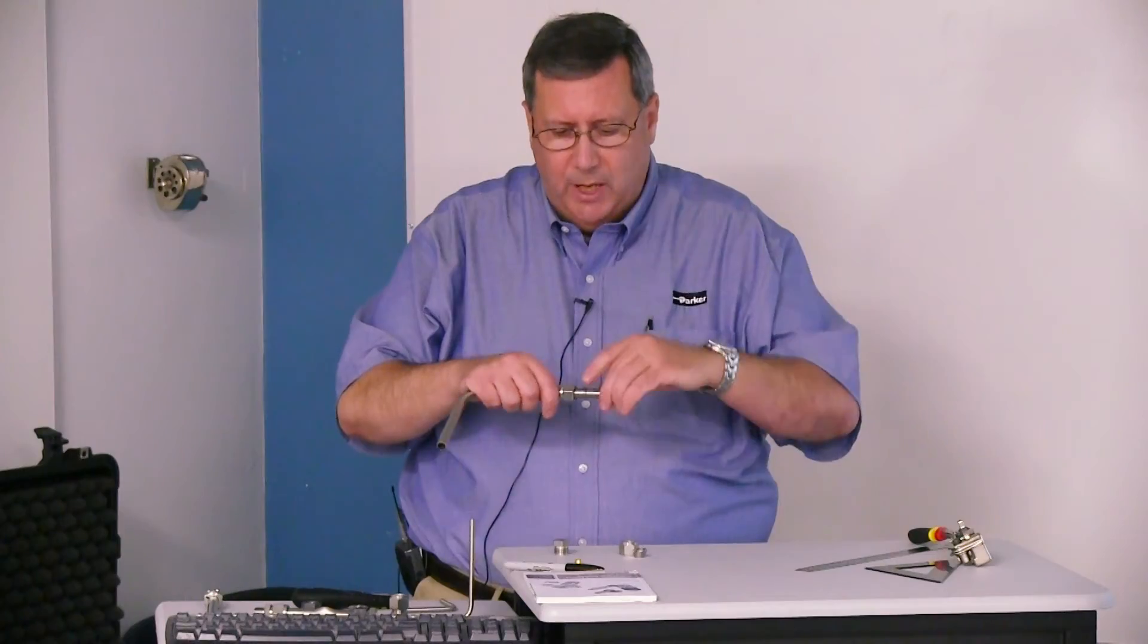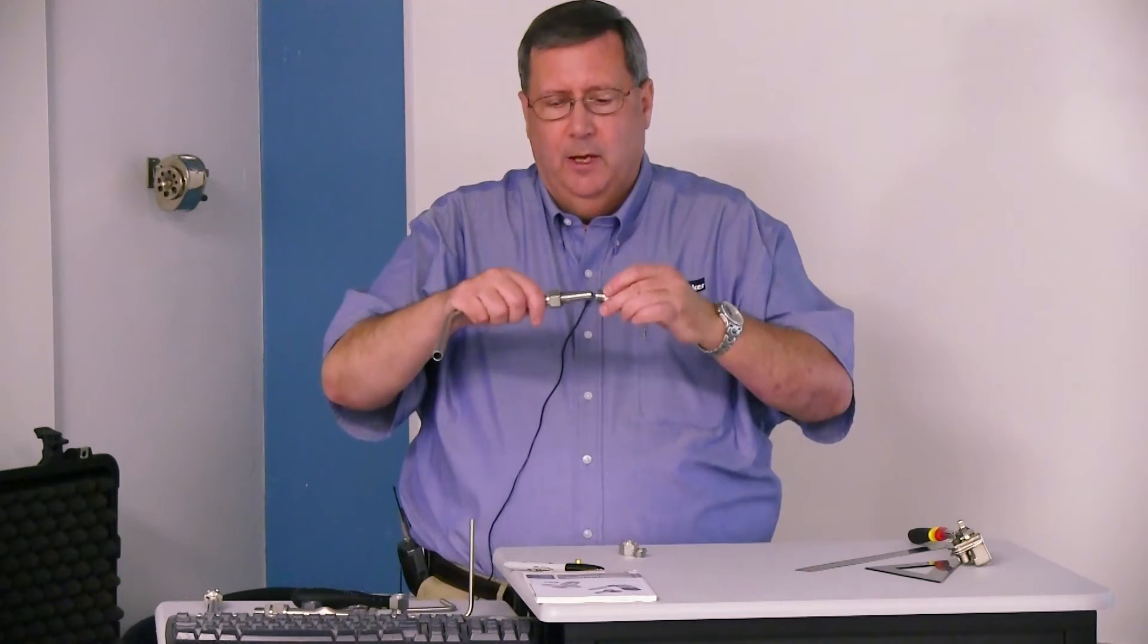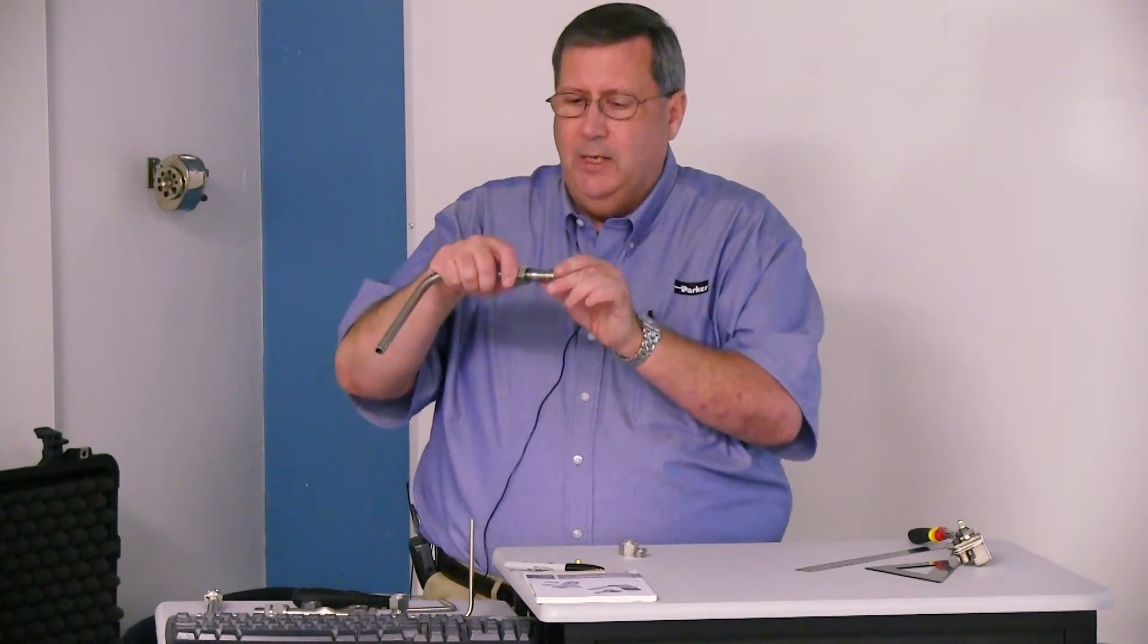then put the rear ferrule on, then the front ferrule, and use that little piece of tubing as a pilot. Put it in the fitting body - or this could be the actual piece of tubing you fabricate. Take a look at that.